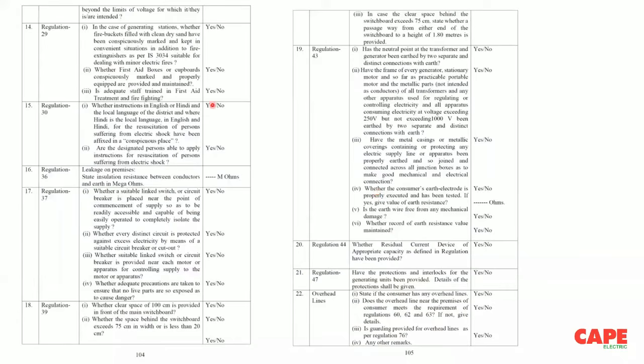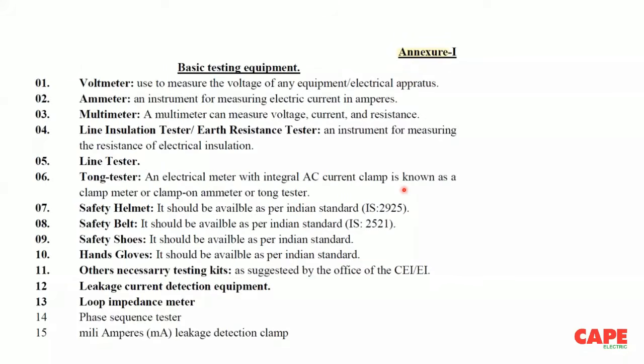However, these formats are already given in the standard in order to do verification by the chartered electrical safety engineer, and the chartered electrical safety engineer shall also carry certain meters. Say, for example, one of the new incoming is a loop impedance meter. A fault loop impedance meter is also required. But again, for a larger industrial installation or a medium-level industrial installation, these basic testing equipments are actually not sufficient to make an electrical safety audit or electrical safety verification. Probably you can make an audit, because audit is only partial. Verification is not possible. Why I show this: there is one more regulation which I will refer to a little bit later so that you will be able to understand the importance.